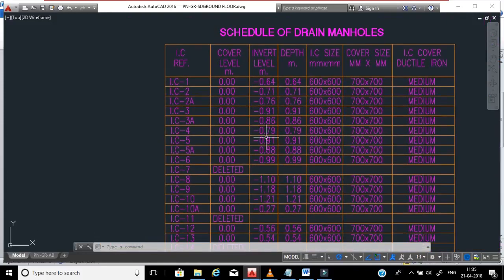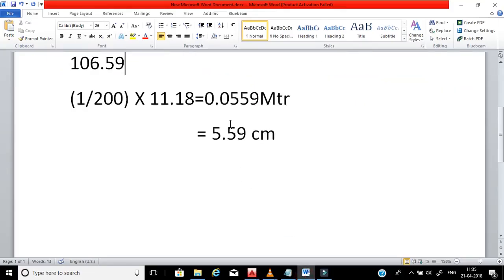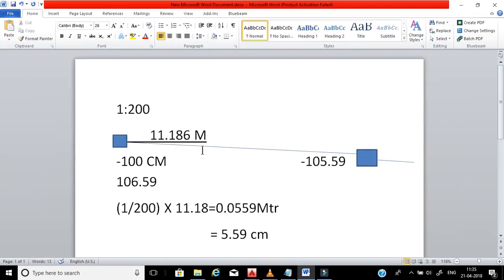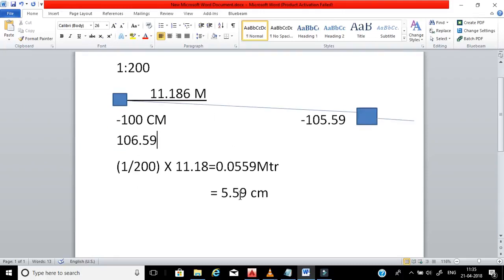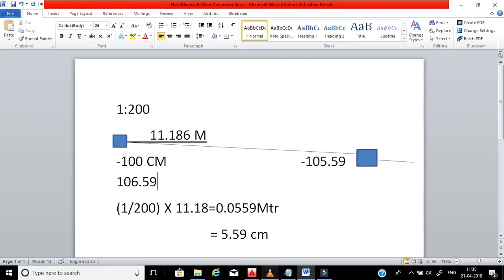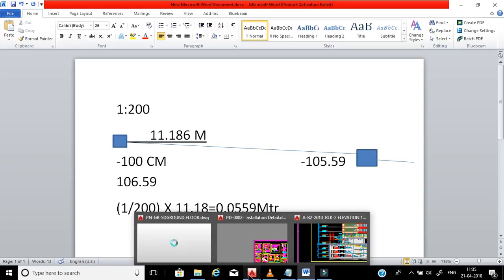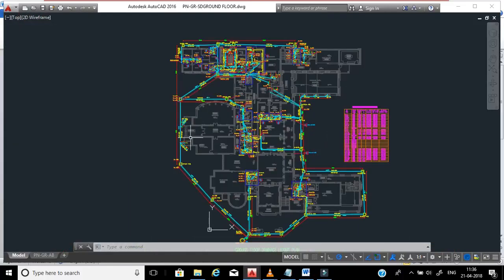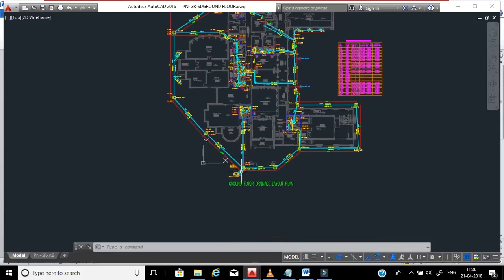When you receive a new drawing and are going to execute a project, you must do this calculation to check for any mistakes. The consultant or draftsman preparing the drawing can make mistakes. You should double-check whether all manhole levels are correct. If the manhole level is wrong, the pipes may not match with the external manhole, or it may be too deep to connect to the external drainage.